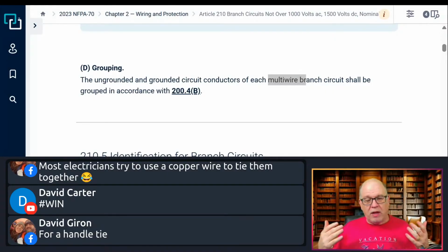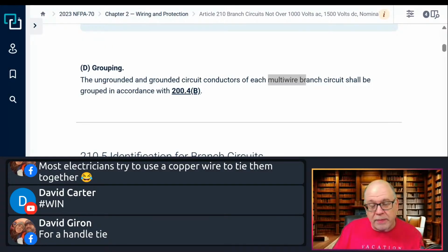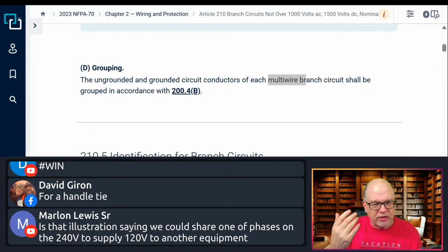And people say, well, it may work. Yeah, it may work. But if it's a screw and that breaker puts off heat, for example with a lot of loads, and that screw holds the heat because it's steel, then it could expand and cause the handle to break. I don't know. I'm just saying, you really have to.